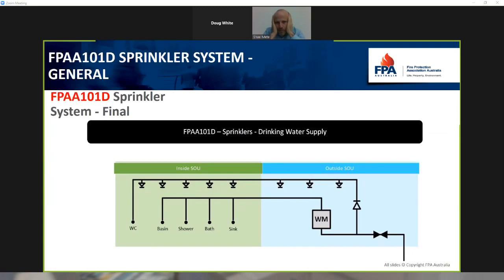This is a schematic. If you haven't had much to do with the system yet, this is a good one because it really demonstrates the whole concept of the system and what's connected to what in a really simple manner. On the left-hand side, the green section is the single occupancy unit, the SOU, and the right-hand side is all of the areas outside the SOU. You can see that the WC there is the toilet. You can see the toilet is fed from the sprinkler system. This is a new concept to the NCC. And there's your water meter, obviously, which still picks up all of your plumbing fixtures, but there are two separate feeds that feed the SOU and the outside of the SOU, all of the sprinklers, from an independent supply with its own backflow connection.